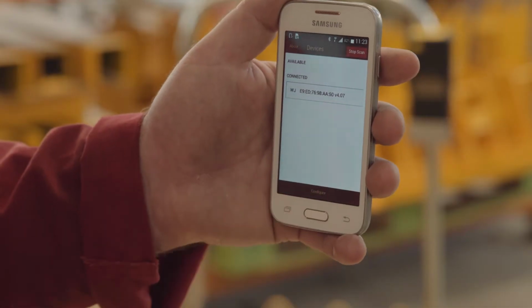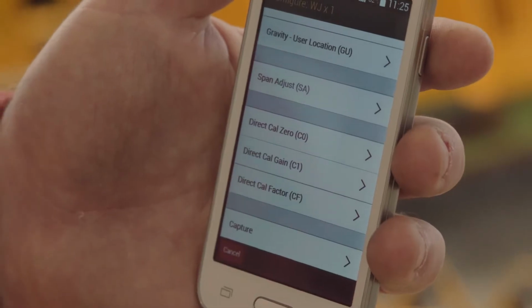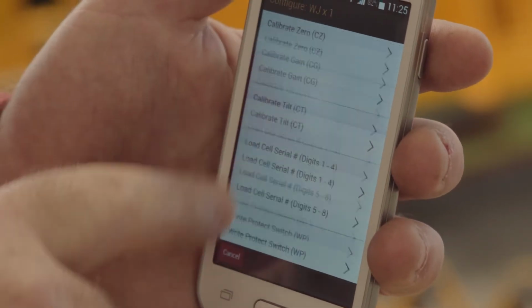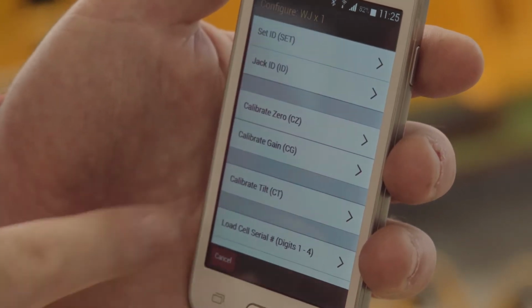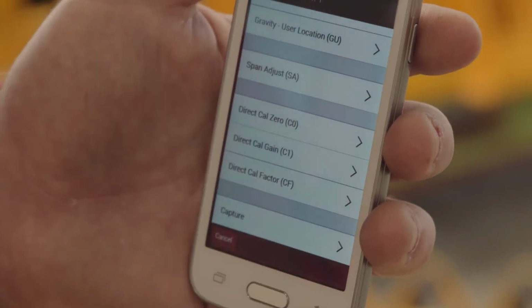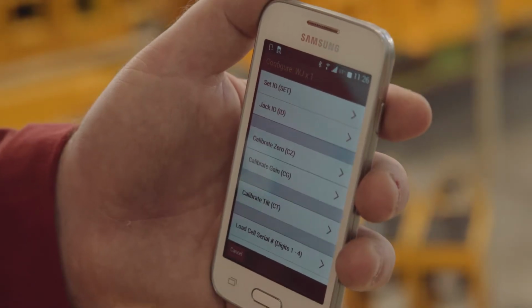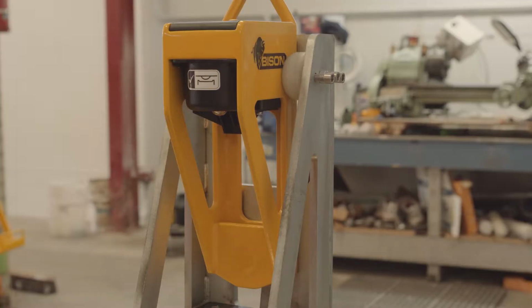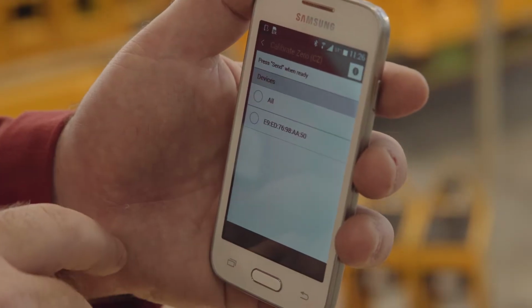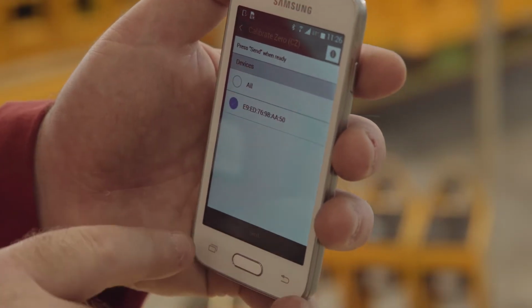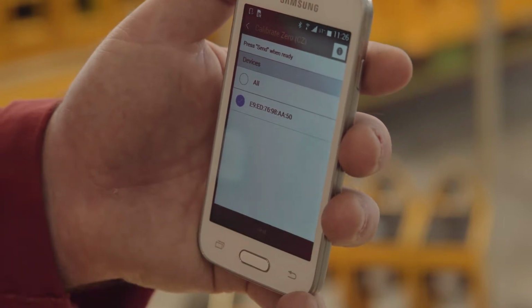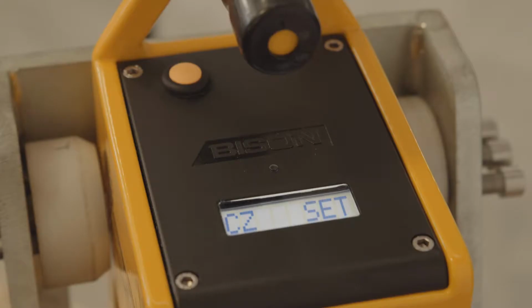Press Configure to continue. The app will now show you a menu with all of the available configuration options. A full description of the options is available in the user guide. The first step in the calibration process is to set the 0. With no load on the scale, choose Set 0 on the app. Select the scale and then press Send. The scale will show CZ Set.